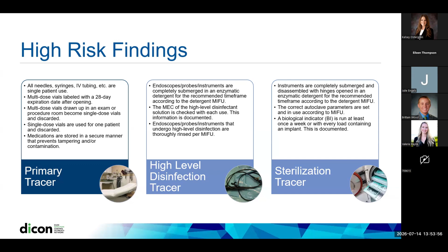And then for sterilization, again, really focused on manual cleaning, making sure that there's full submersion of that instrument in the enzymatic detergent, using the correct autoclave parameter as outlined by the instrument IFU, and utilization of a BI at least weekly, preferably daily, and correct documentation of such. So if any of those things, like Brittain mentioned, if they don't document the BI, we have no idea, as the true test of sterility, if that cycle passed, then we'll go back.